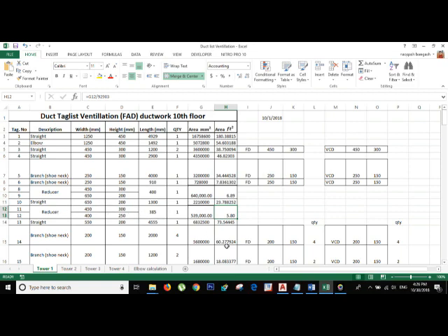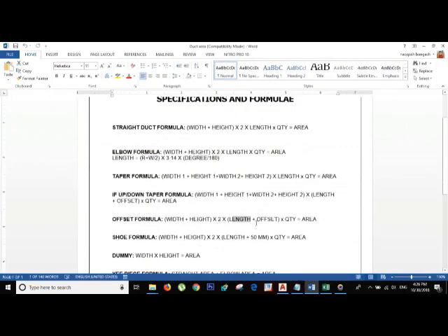For example, if the duct length is 400 mm and the offset is downward about 200 mm — meaning the distance between the upper duct and the lower duct is 200 mm — then add this offset distance to the duct length. That gives you the total length of the offset duct. The rest of the formula is the same as a straight duct.